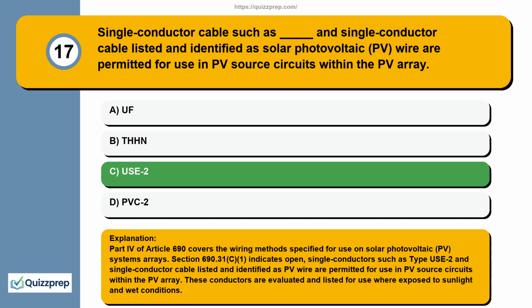Part 4 of Article 690 covers the wiring methods specified for use on solar photovoltaic, PV, system arrays. Section 690.31(C)(1) indicates open, single conductors such as type USE-2 and single conductor cable listed and identified as PV wire are permitted for use in PV source circuits within the PV array. These conductors are evaluated and listed for use where exposed to sunlight and wet conditions.